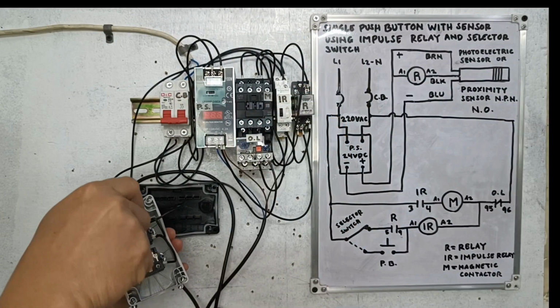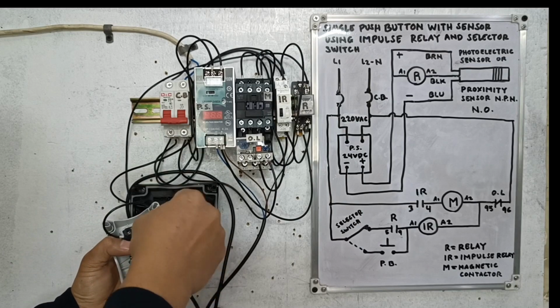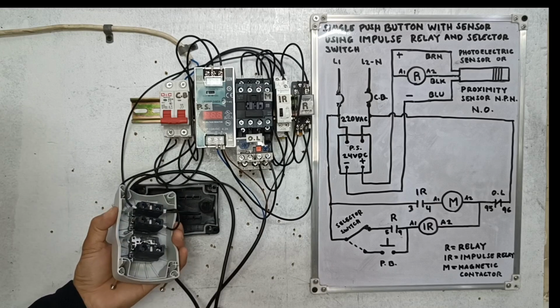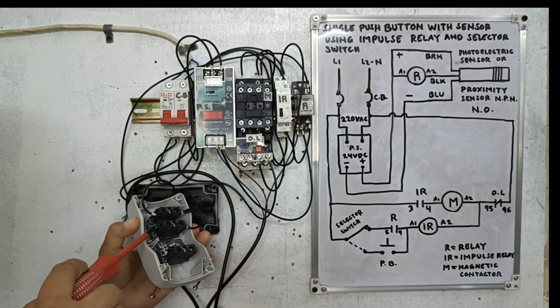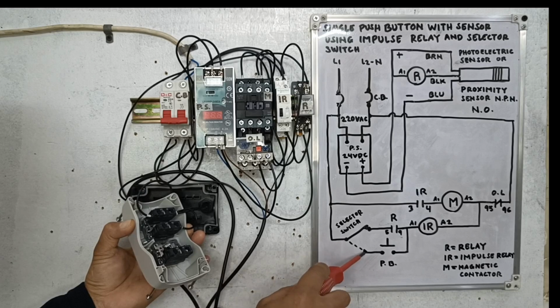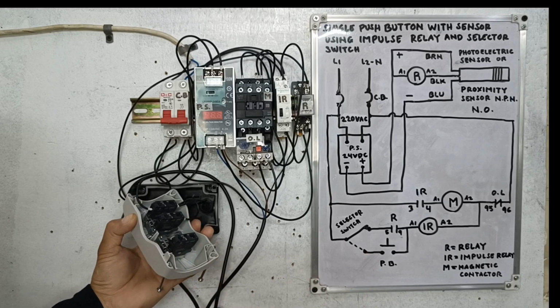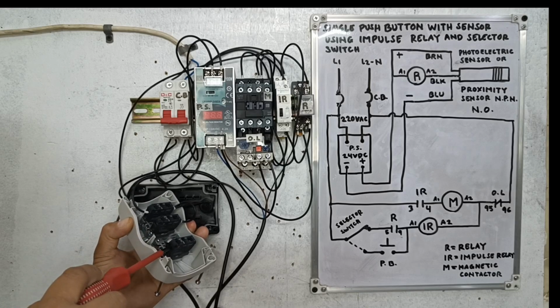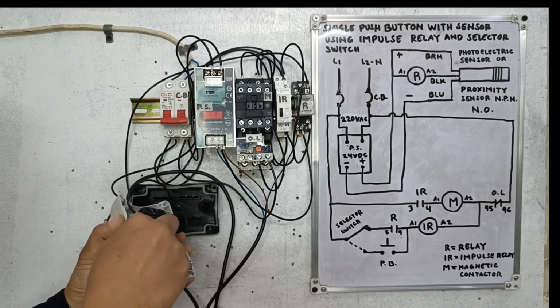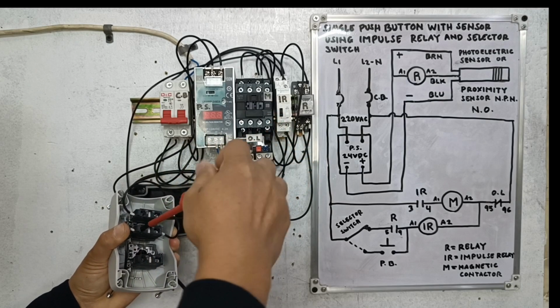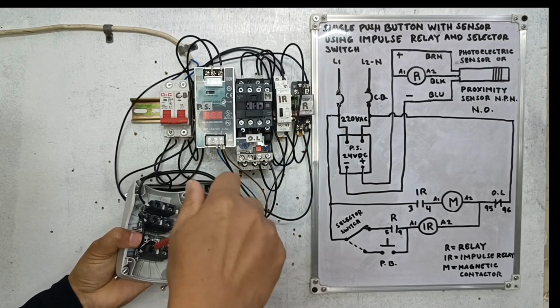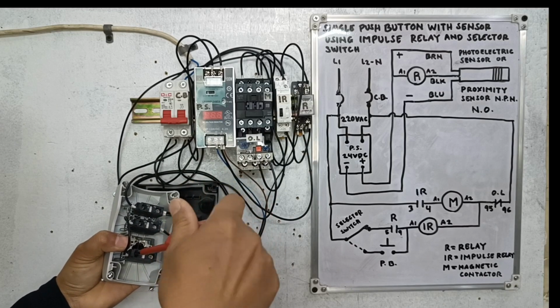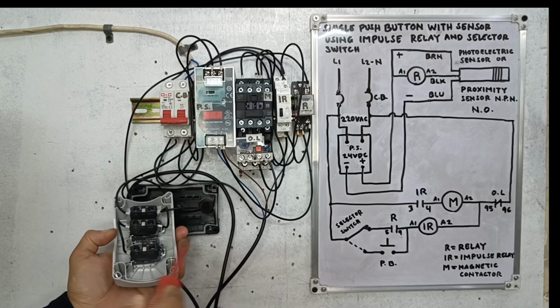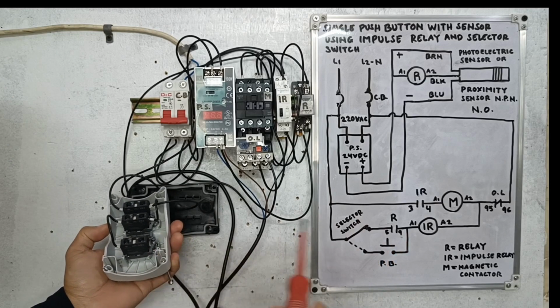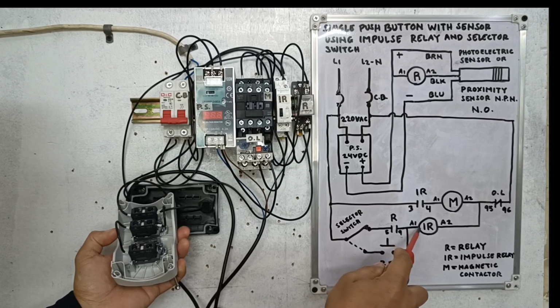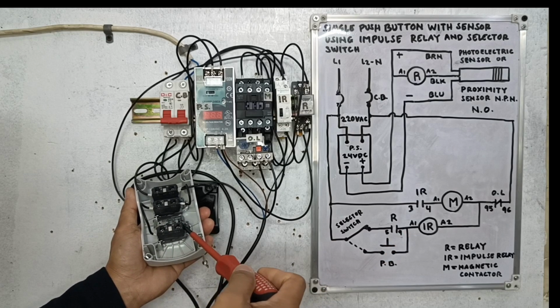So we are going to remove this one, guys. We remove this one first so that we are not confused. So we are going to put now from the selector switch, from here to here, to the push button. From here to here. We can tighten. Here also, tighten. The next, from here to the push button, going to A1 of the impulse relay, from here to here.